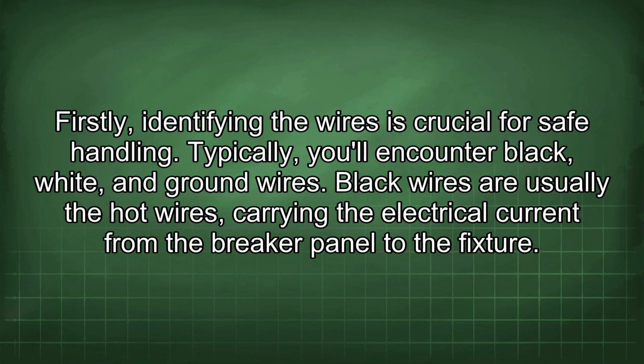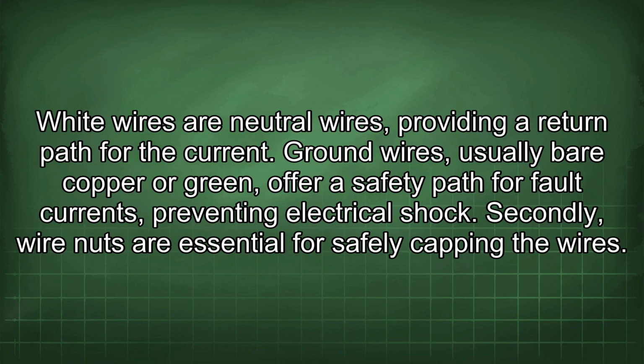Firstly, identifying the wires is crucial for safe handling. Typically, you'll encounter black, white, and ground wires. Black wires are usually the hot wires, carrying the electrical current from the breaker panel to the fixture. White wires are neutral wires, providing a return path for the current. Ground wires, usually bare copper or green, offer a safety path for fault currents, preventing electrical shock.